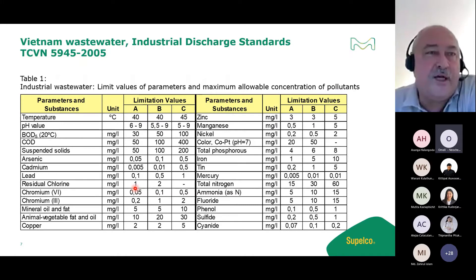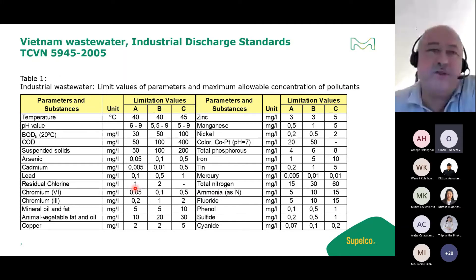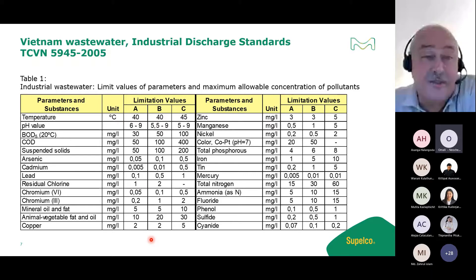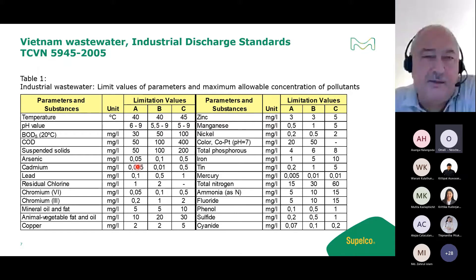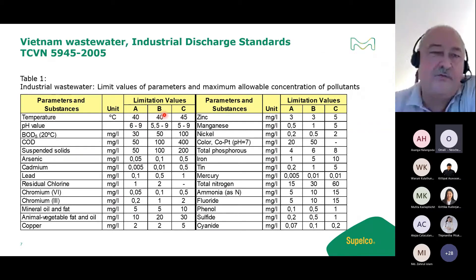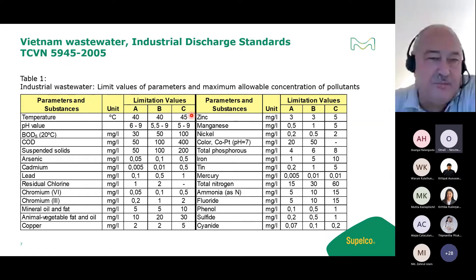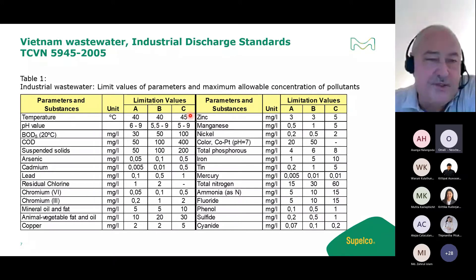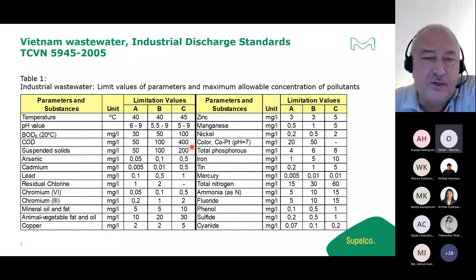Another example is from Vietnam's industrial discharge standard. They have different requirements depending on industry segment and discharge class. For a Class A water discharge, COD is 50 mg/L; for Class B it is 100 mg/L; and for Class C water it is 400 mg/L.